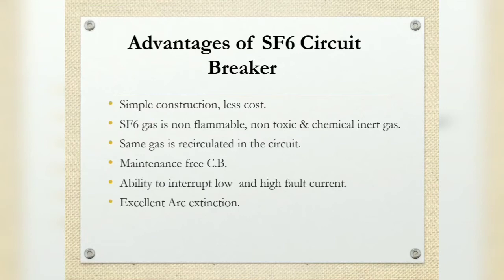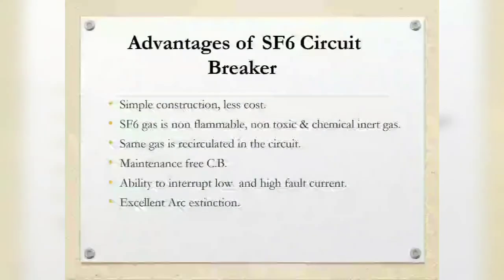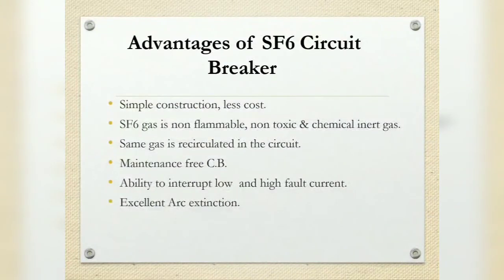The gas is non-inflammable and chemically stable, so there is no fire hazard. Its decomposition products are non-explosive, and hence there is no risk of fire or any explosion. Electrical clearance is very much reduced because of the high dielectric strength of SF6.